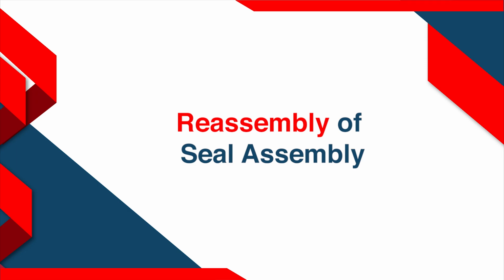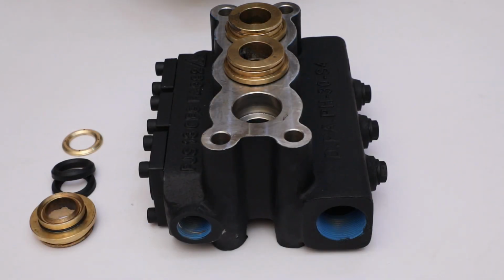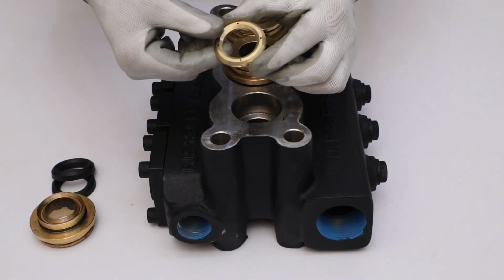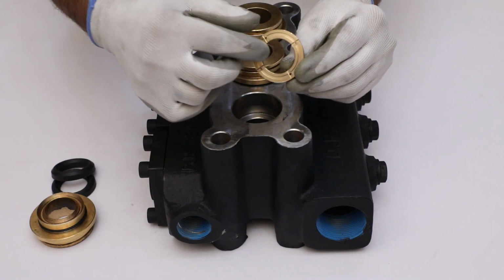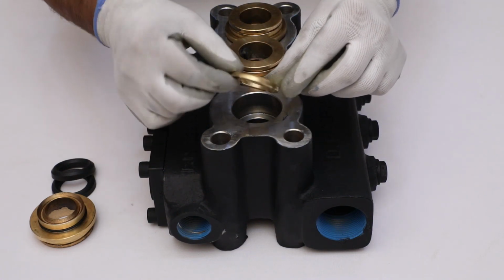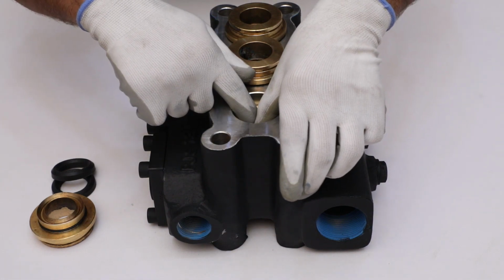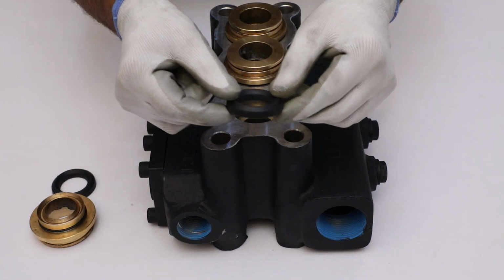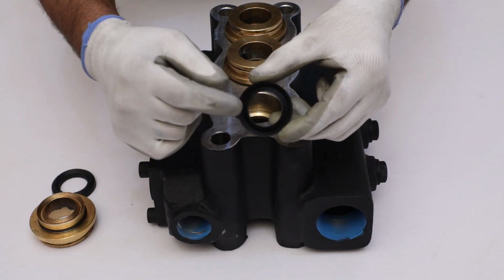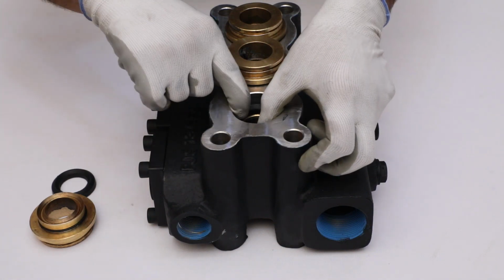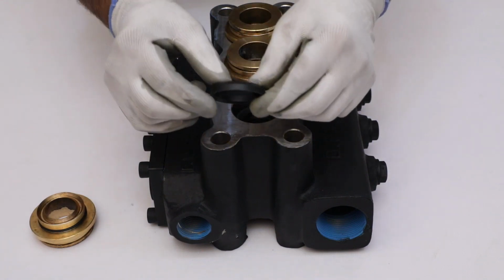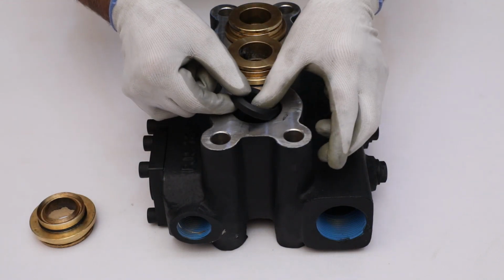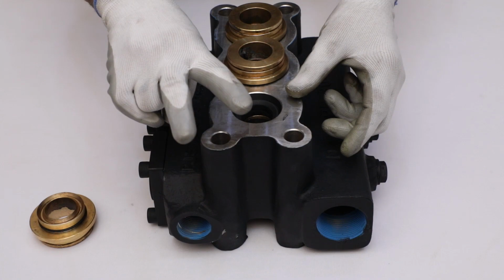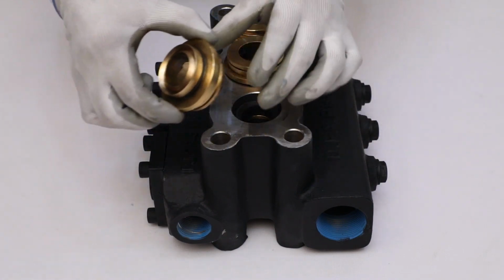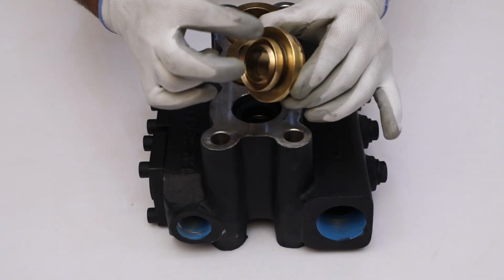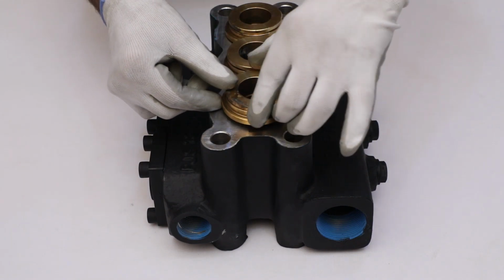Reassembly of seal assembly. Firstly, place packing ring facing groove side down into the pump head. After that, place two chevron type plunger seal facing groove side to the packing ring respectively. Assemble packing support pump head in such a way that grooved surface will match with the plunger seal.